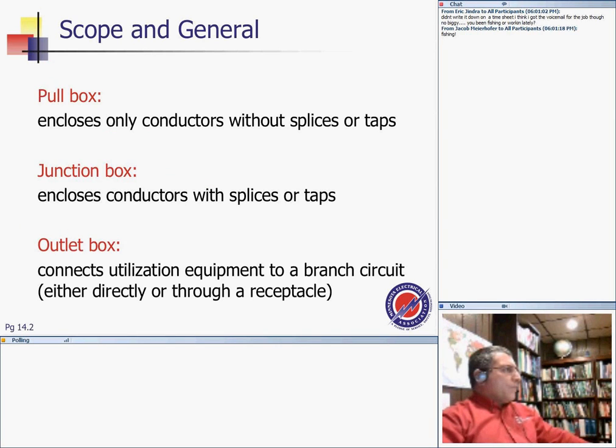So that basically is my J box. Pull box: a pull box encloses only conductors, without splices. To be a pull box, guys, the conductors have to be number 4 or larger. Here's a conductor. This is Mr. Conductor. Mr. Conductor has to be number 4 or larger in order for the box to qualify as a pull box.